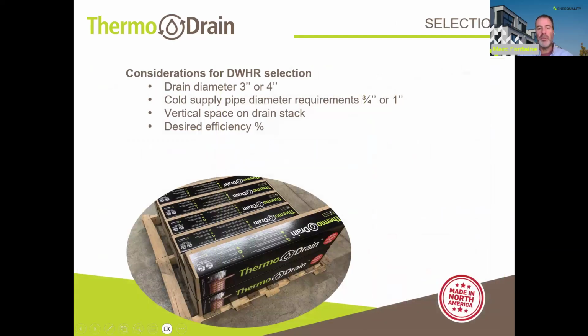One of the important things to know when selecting a drain water heat recovery unit is that if we're looking at a 3-inch or 4-inch drain stack, most manufacturers limit the selection of the drain diameter to that. And then if you need to supply a 3/4 inch or 1-inch line size for your cold water supply, if you have bigger than 1 inch, there are some ways around that. We can look at projects and give information on how to do that. Make sure that we have the vertical space for the drain stack. Drain water recovery units range from the 30-inch unit size to upper lengths of the 70-inch length size. Most of the units are roughly 48 inches in length for more performance, and 33 inches in length for the regular performance, if I can say it that way.